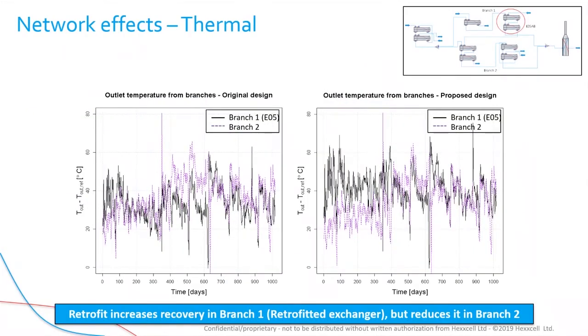Here I'm showing just this. On the left-hand side, we have the outlet temperatures of the two branches in the original design, black for branch 1, purple for branch 2, whereas on the right we have the same graph for the proposed design. This clearly shows that the retrofit increases the heat recovery in branch 1, but reduces it in branch 2. Interactions are not limited to heat exchangers directly connected to each other, but they do have a knock-on effect also on other heat exchangers in the same network. This is in terms of inlet temperature and flow distribution across the branches, which in turn impacts the fouling behavior. Therefore, these interactions can be non-obvious, let alone being able to quantify them. These dynamic simulations allow us to do just this, quantify interactions and benefits of a new design as a part of the entire system.